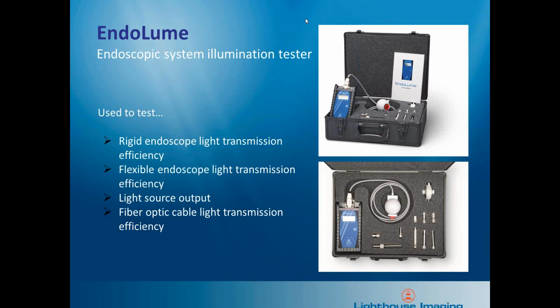So with any of these fiber optic components, the endoscopes and the cables, it's really the transmission efficiency you're most interested in—the output divided by the input times 100 to make it a percentage. You really care what portion of the light coming into the device makes it through. As we'll see in the demonstration, it's not uncommon for only a few percent of the light made in the bulb or LED source to actually make it through into the patient.